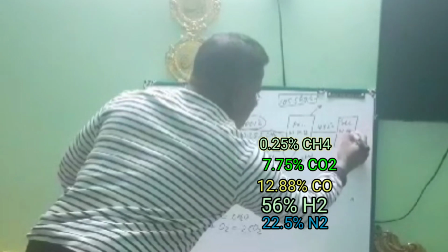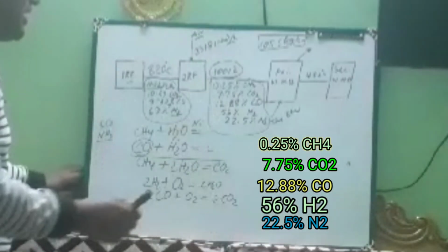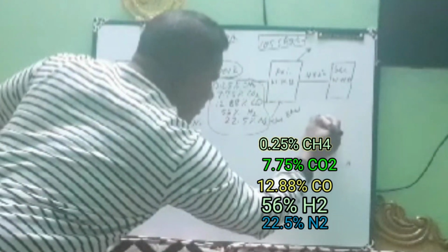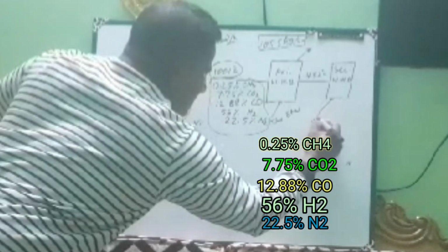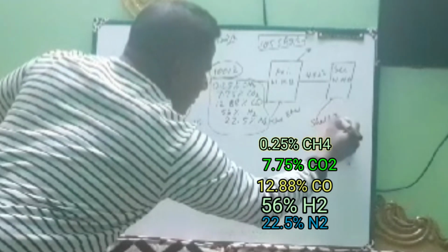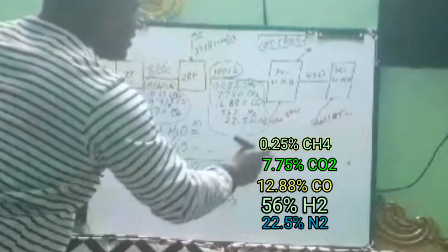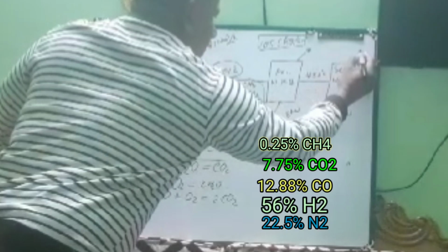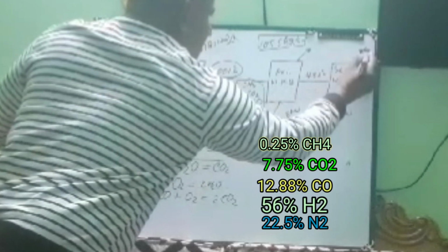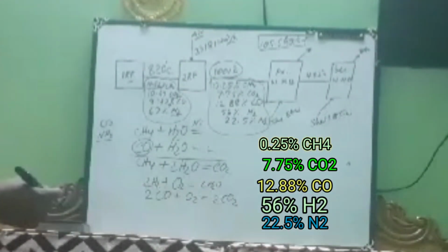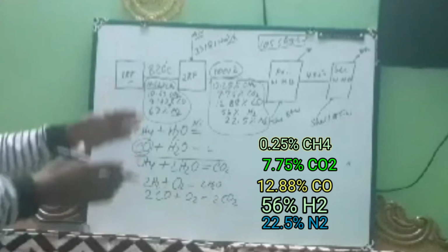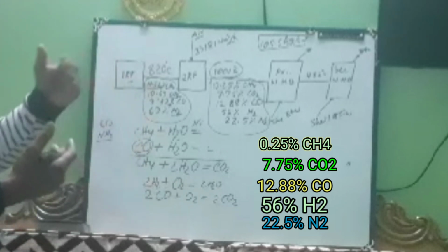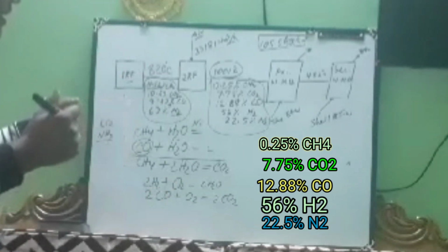On this secondary waste heat boiler, the process flow will go to the tube side and the shell side will be provided with boiler feed water. This is different. The shell side gets boiler feed water, and this water will take up temperature and again go to the steam drum. In this way, the process flow temperature decreases and steam is produced from the process.